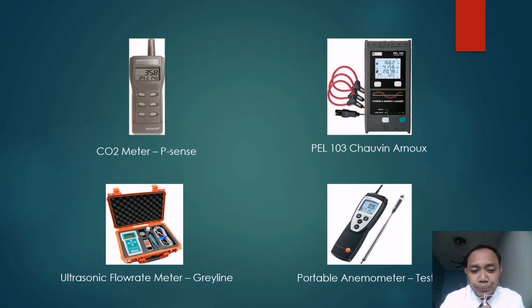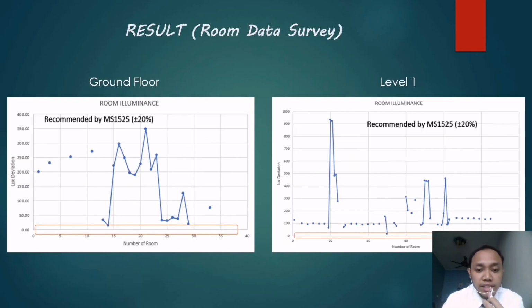For the ultrasonic flow rate meter, Greyline, it is used to measure the velocity in the water. The portable anemometer is used to measure the velocity in ducting such as AHU ducting, and to estimate the amount of supply air. This is the result for my project.